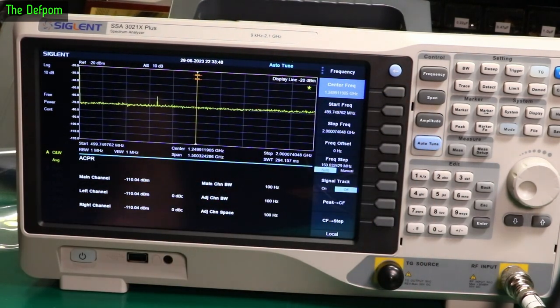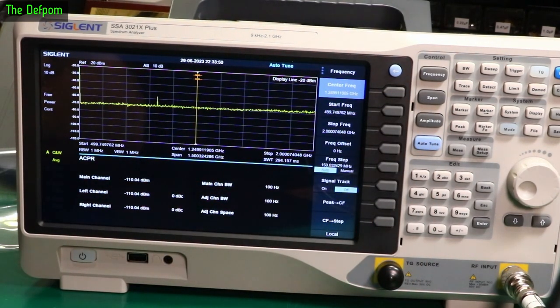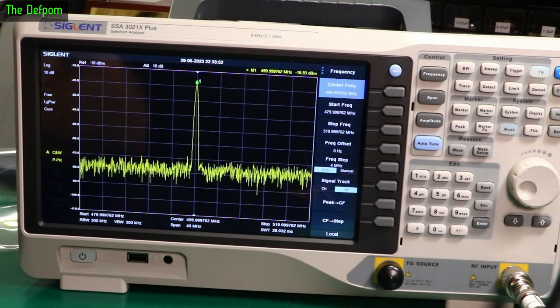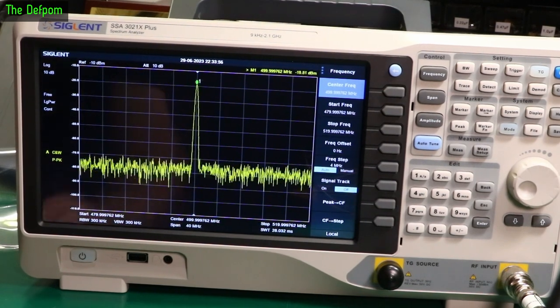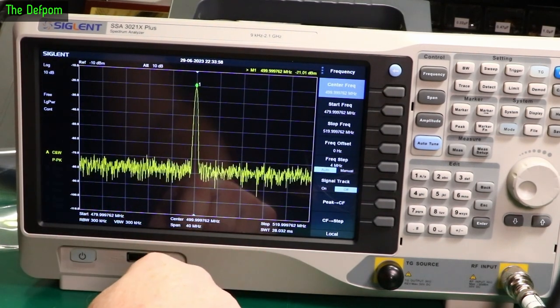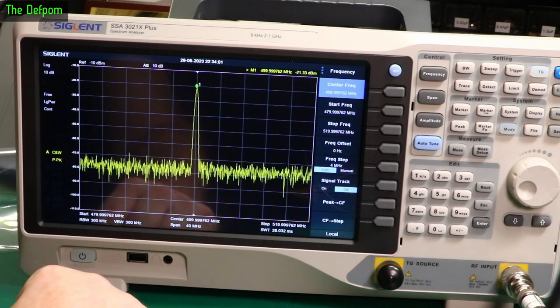Auto-tune. See what auto-tune does. There you go. Found it. That works all right. And it's set the span to 40 megahertz. And resolution bandwidth 300 kilohertz.